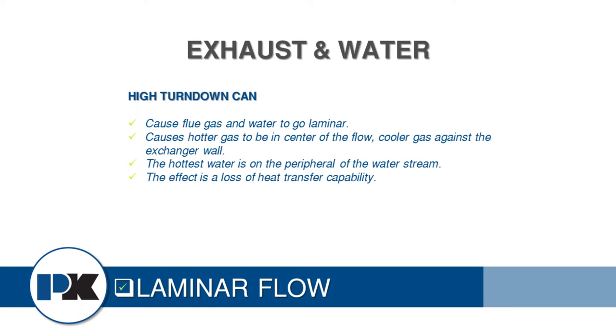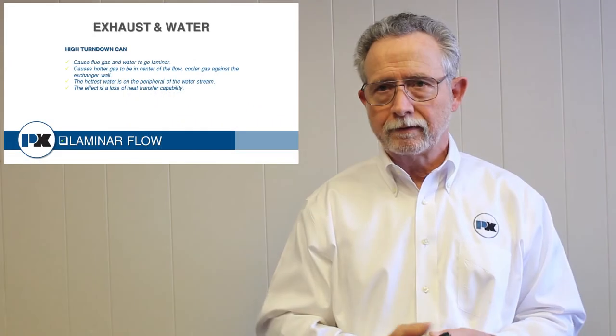There are other factors that impact efficiency. When we do an excessive turndown, slowing the gas down through the boiler can cause it to go into laminar flow — basically a flow with no turbulence. The gas volume going through the exchanger goes straight through with no blending; the outside of the gas stream gives off heat to the heat exchanger surface, but the center of the gas flow remains the hottest part because there's no way to blend it outward.